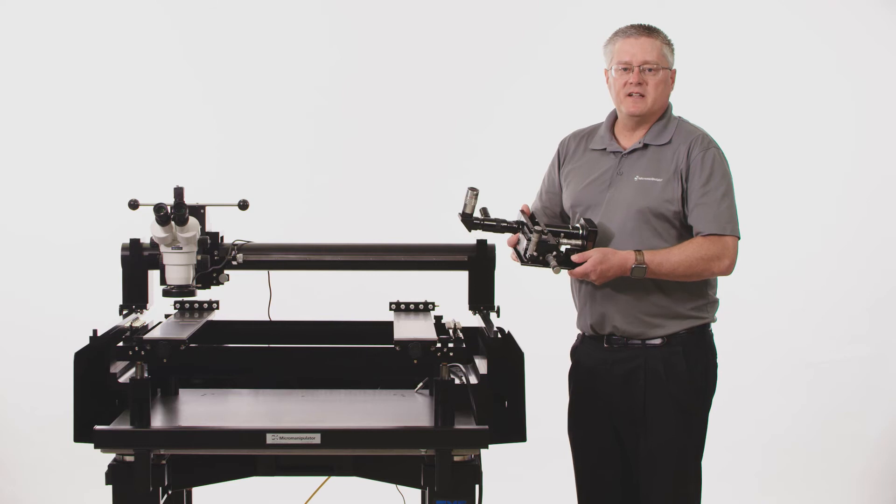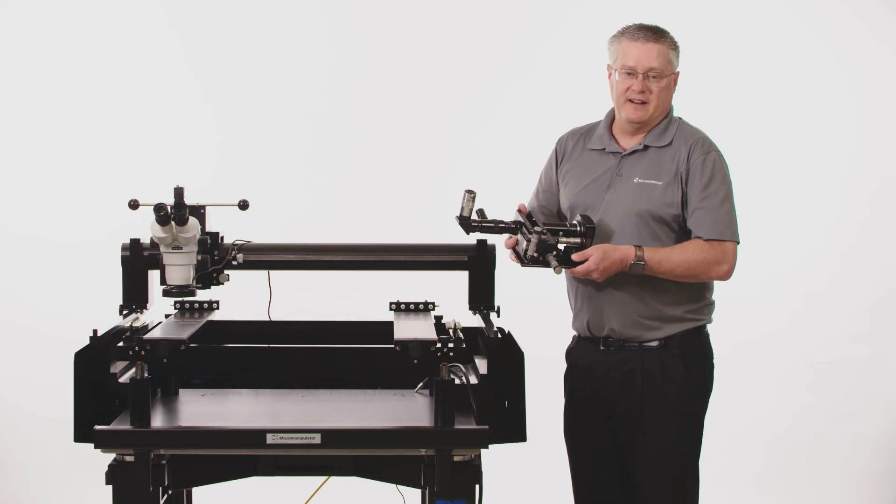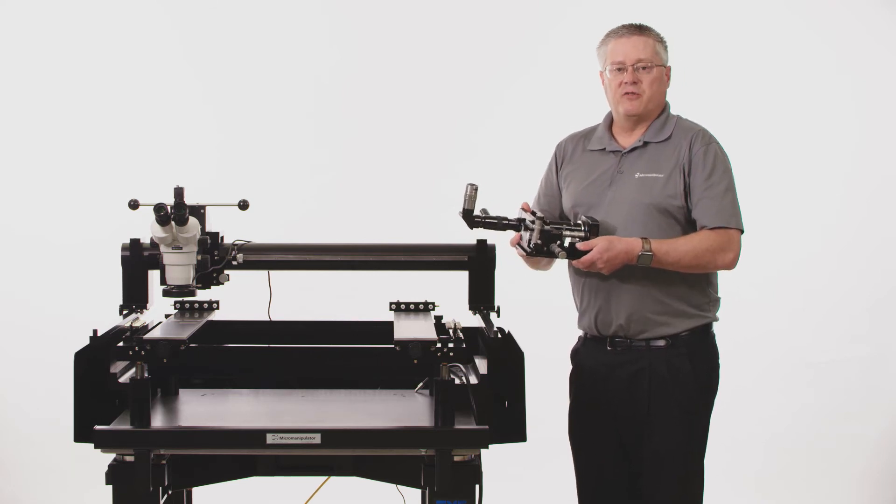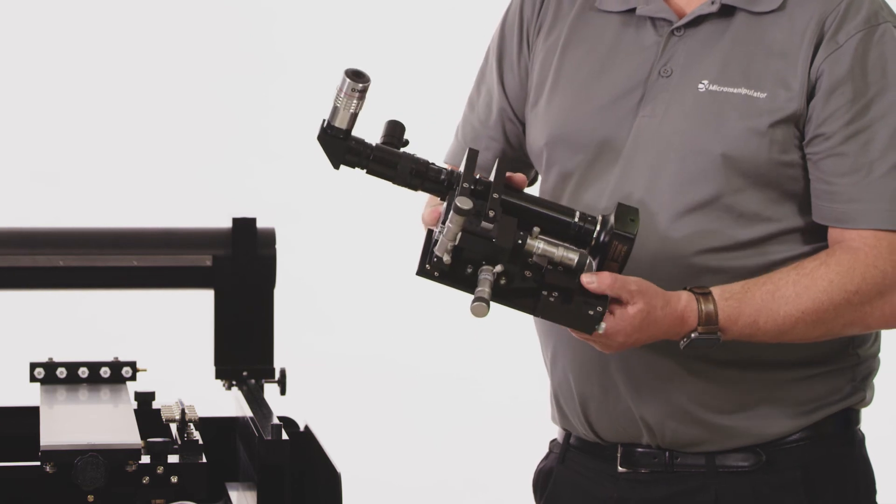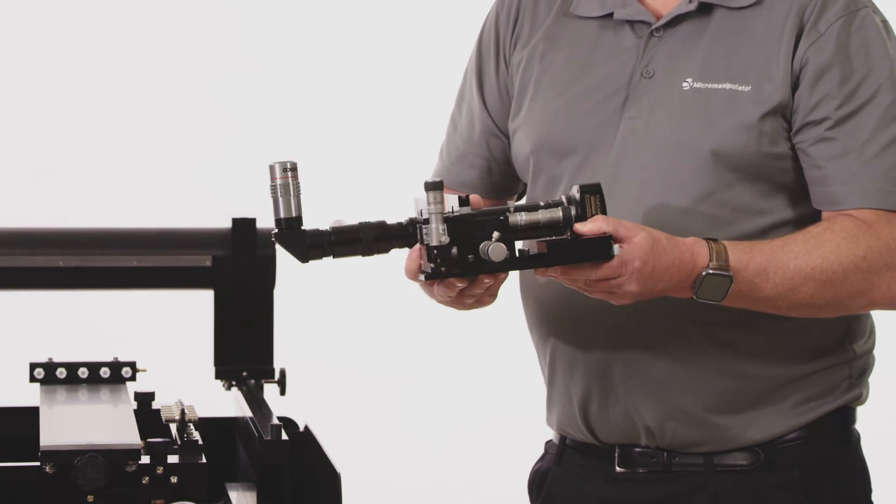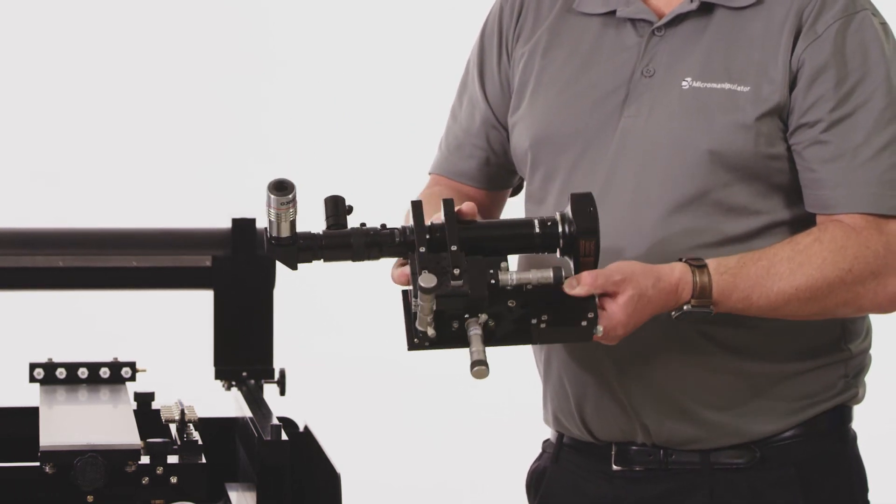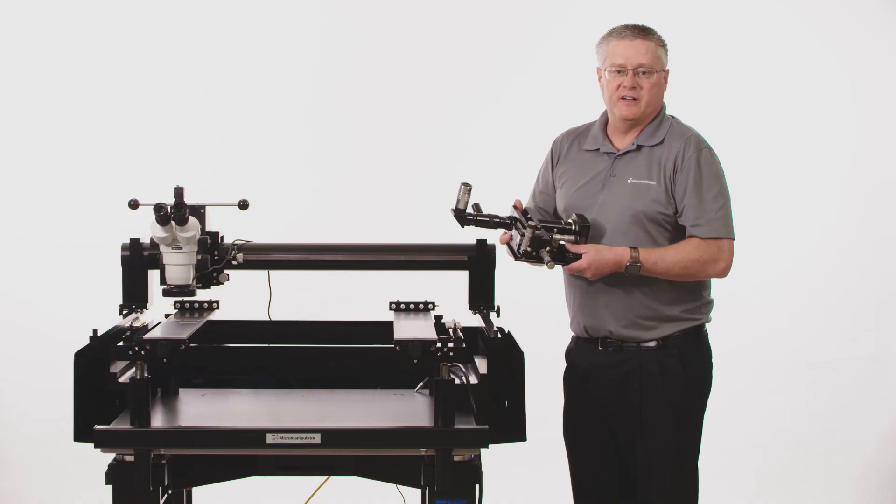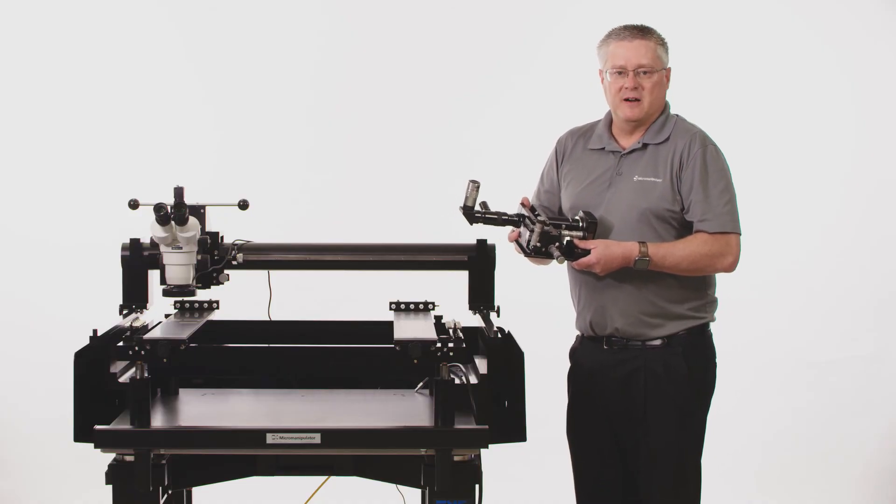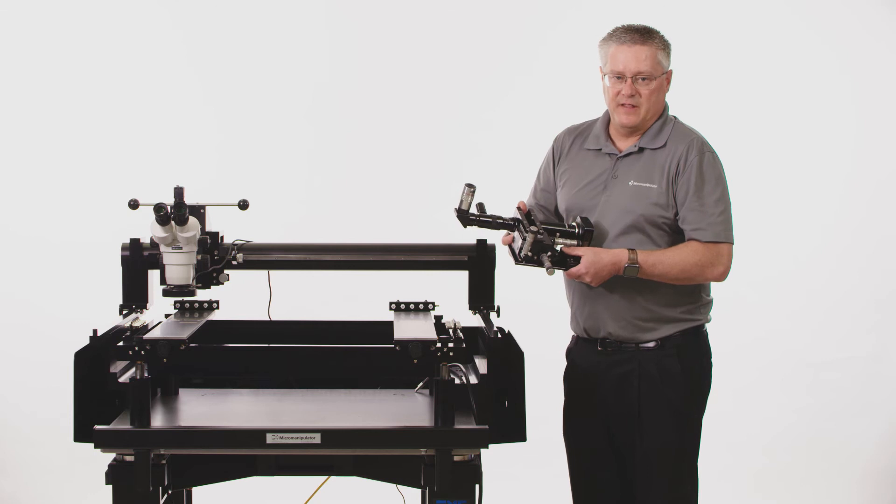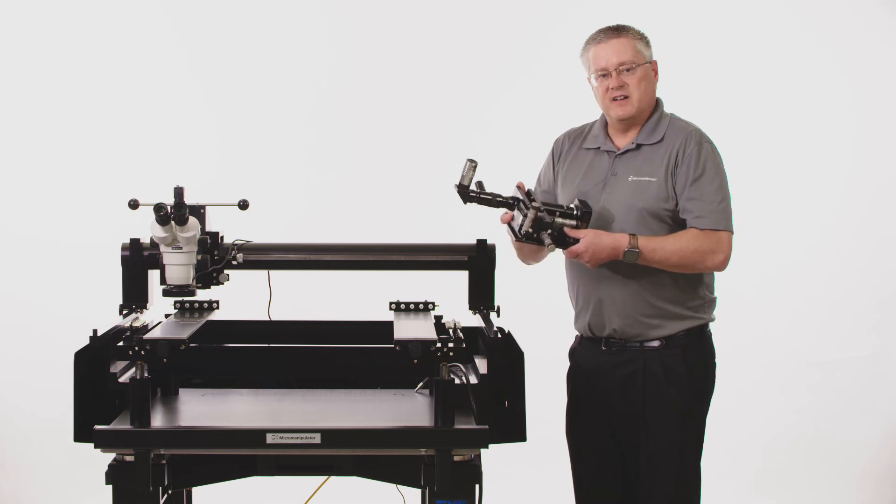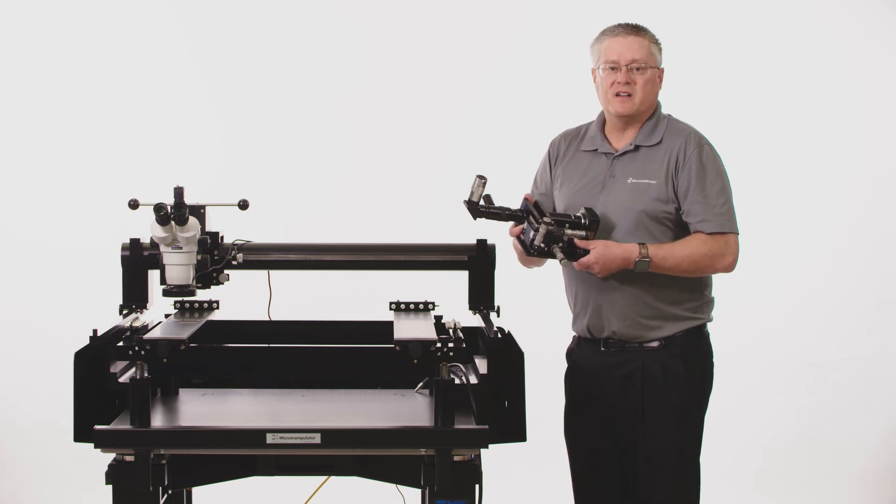The Versa can be easily configured for double-sided probing and imaging as well, allowing you to probe from both sides of the device simultaneously. Perhaps you maybe need to do some special imaging from the top for photo emission or whatever your application requires. The Versa can be configured for that. What I'll show you here is how you configure it for that bottom-side up imaging.